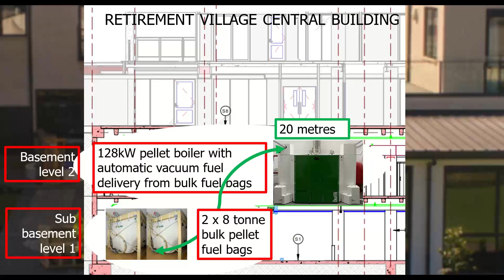On the ground floor, we're going to have deliveries for the blower truck to connect to. So there's a permanent line that goes from a service bay wall down to the sub-basement to fill those bags up. They'll be in place, filled up with pellets, and then automatically transfer again using air conveying, blowing, from the bags to the boiler.